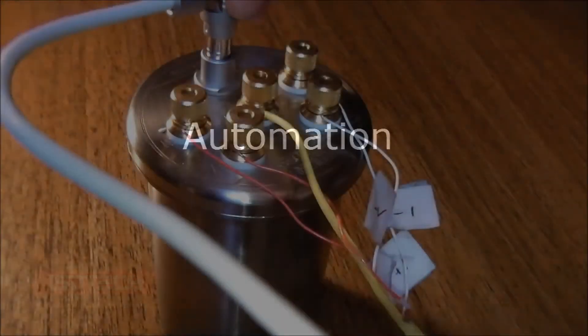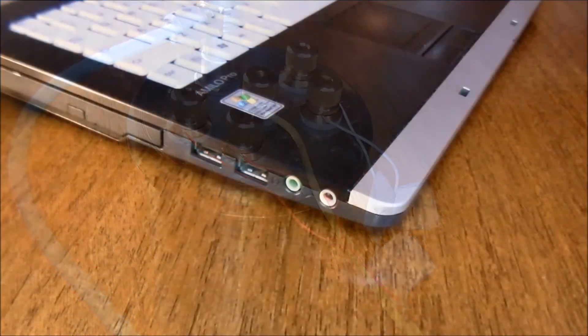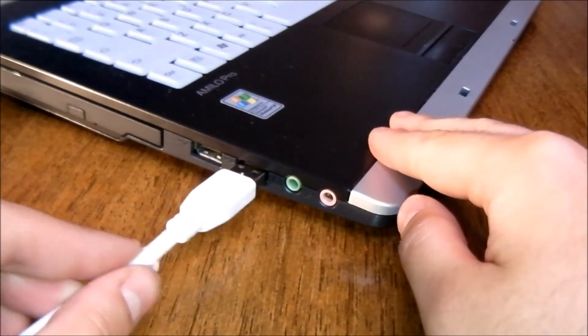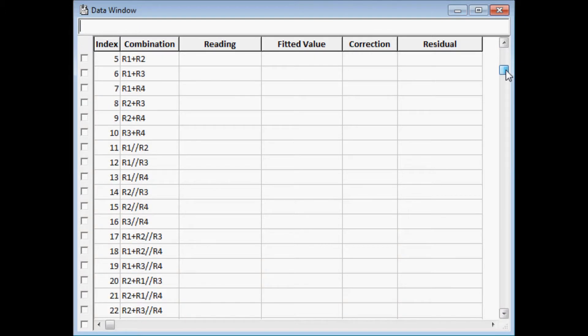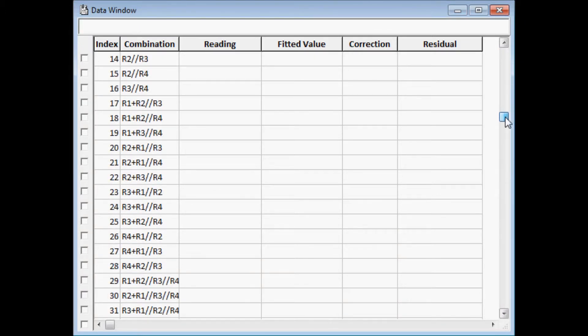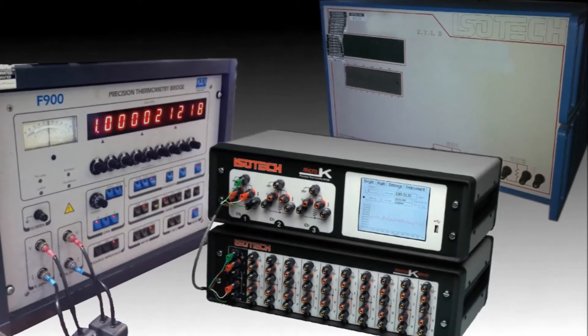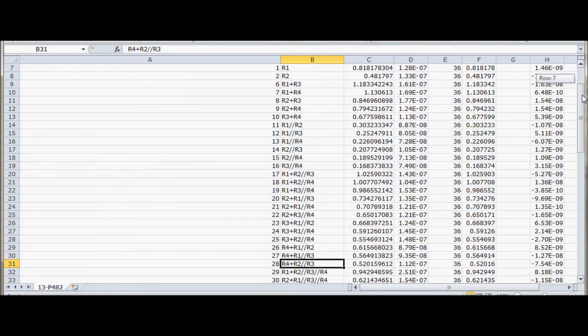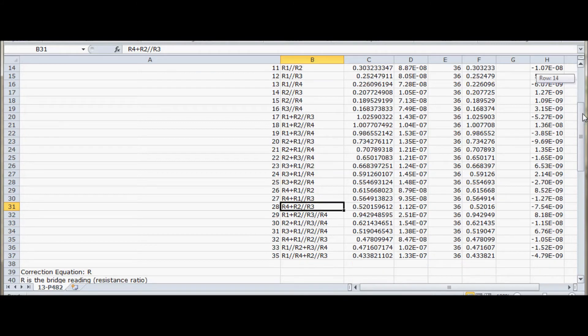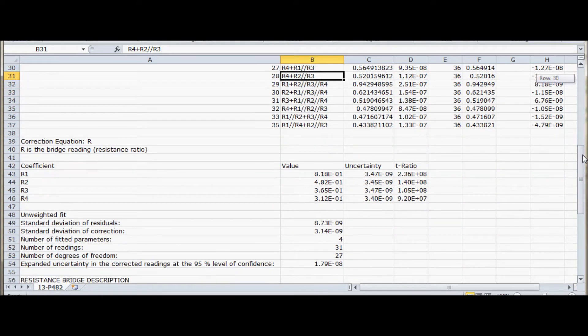The Automatic RBC connects to a PC via a single USB lead. The software can switch the four-terminal resistors to generate 35 interrelated four-terminal resistances. A number of popular thermometry bridges are supported. The software records a number of measurements from a connected bridge, calculates the uncertainty, and can print a full calibration report.